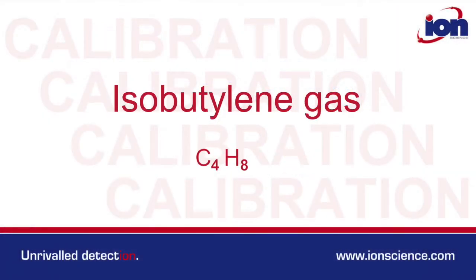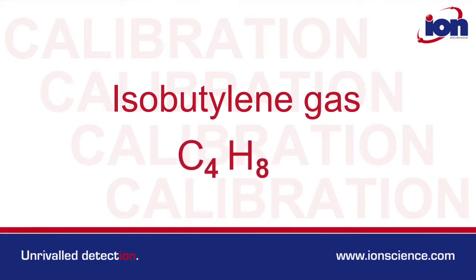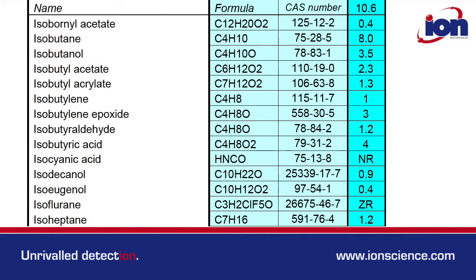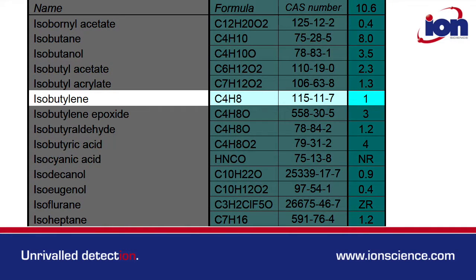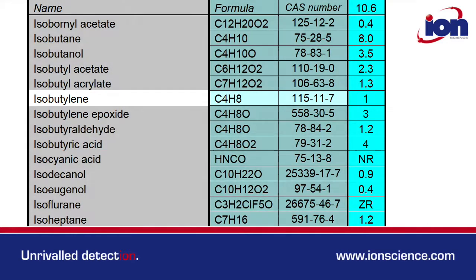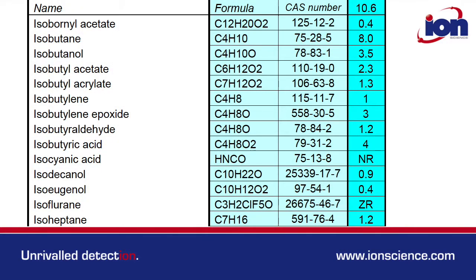Isobutylene gas is commonly used to calibrate PID instruments, as it's relatively harmless at lower concentrations and offers a robust response. Many Ion Science PID instruments are calibrated using isobutylene, which is allocated a response factor of one. Other VOC gases are allocated response factors relative to that of isobutylene.